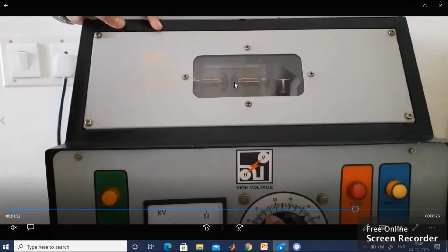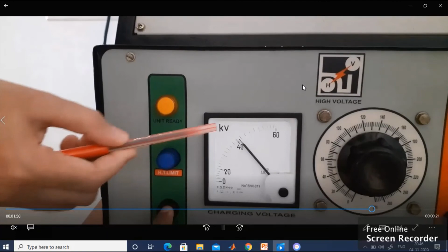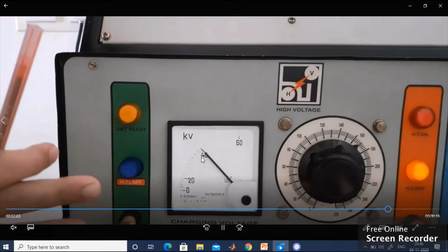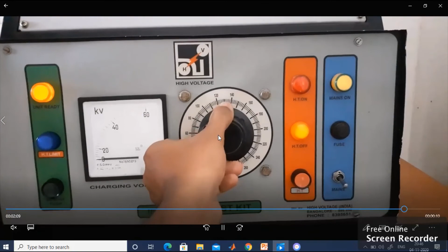Please look here - that means a spark has taken place, meaning the dielectric property has been damaged. The transformer oil lost its dielectric property. Now I have got the breakdown voltage, the breakdown strength, equal to 40 kV.